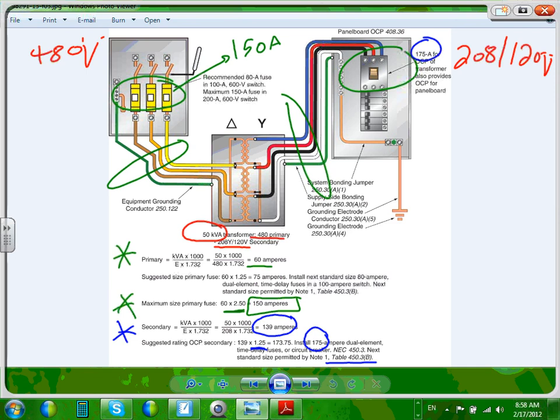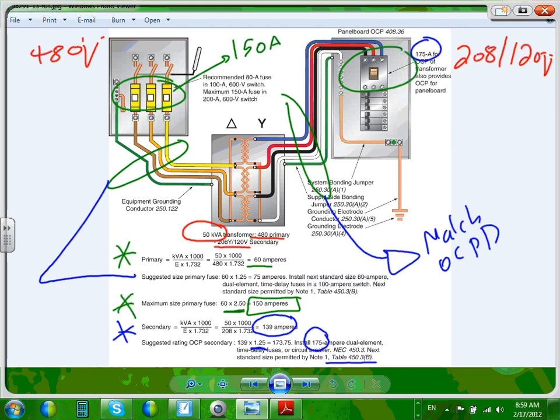The one thing I want to bring to your attention is the way we size the conductor here. See these conductors? Can you guys see the conductors? I always say match the overcurrent protection device on that panel because it's ahead of a panel. Match the overcurrent protection device. On this one here, I usually size it based on 125. So the size of my cables will be 75 amp cable. I don't know what they're using here. 75 amp cable. Any questions about this?